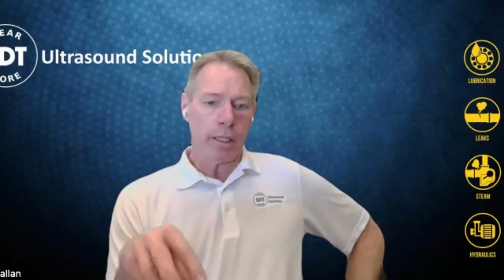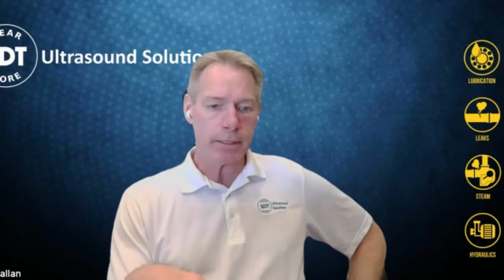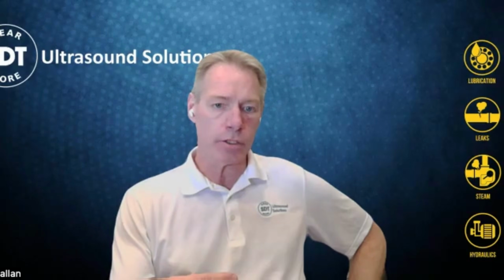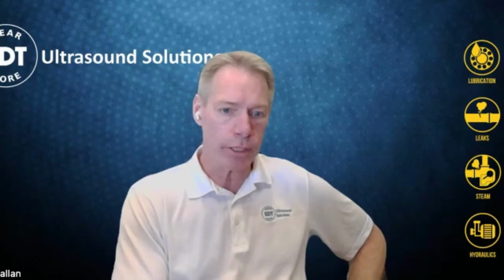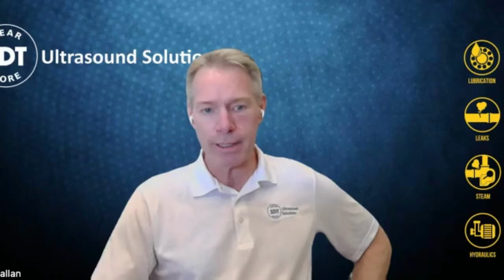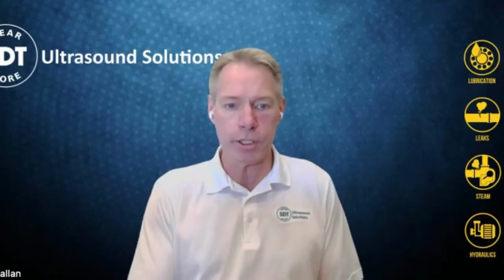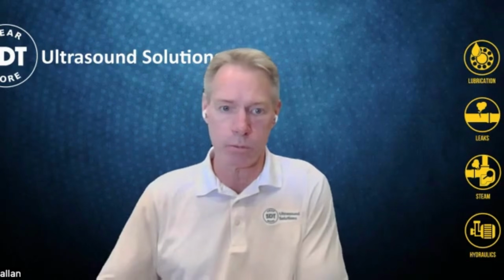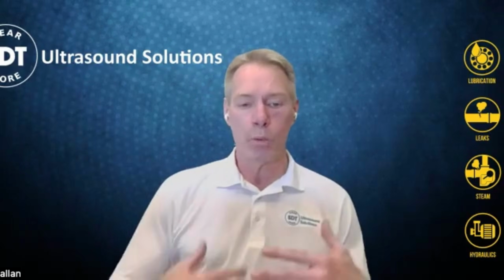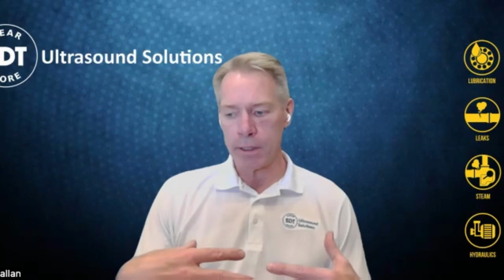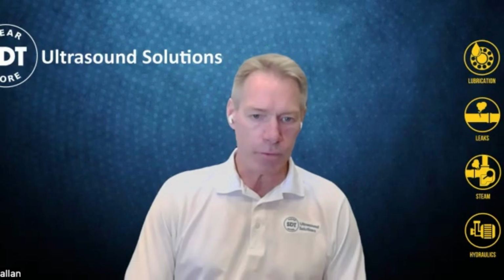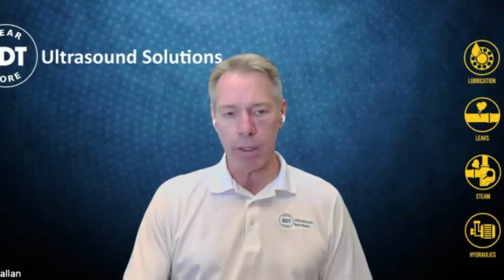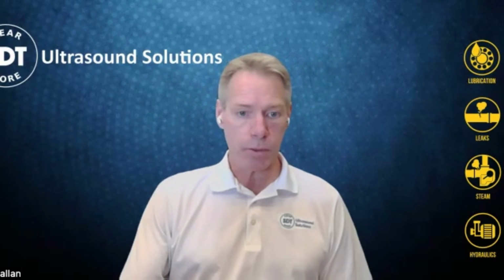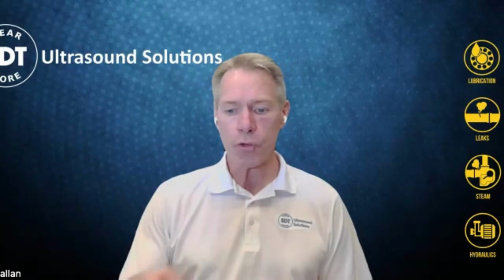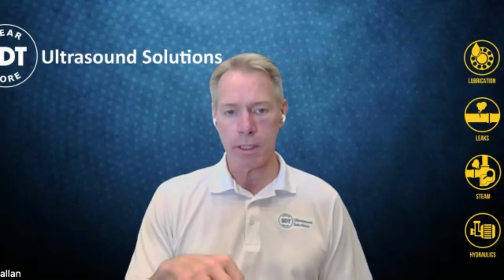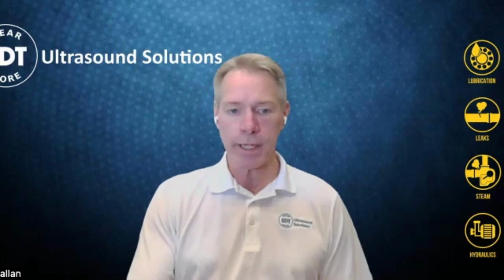So that's part of it. What we had with vibration analysis is we have a technology that we say ultrasound condition monitoring, vibration analysis. So with ultrasound, we're monitoring condition. With vibration, we're going deeper and saying, well, what's the root cause of the problem? What we've done at SDT is we've added in a database of bearings. It's about 50,000 bearing references have been added into our software now. And each of those bearing numbers comes with a unique fault frequency. It's exactly the same tools that vibration analysis has. So we've kind of leveled the playing field.